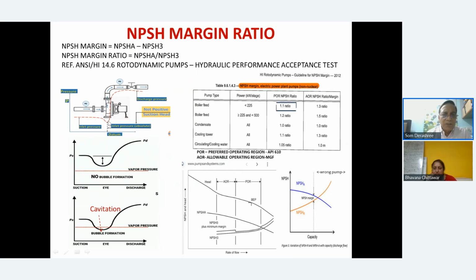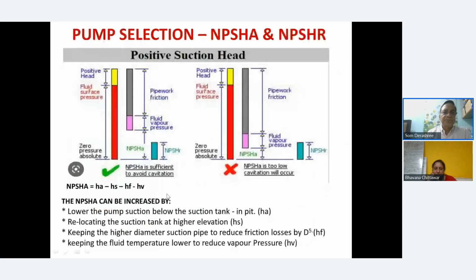Now this fall should stay above the vapor pressure. Let's say this is the vapor pressure line. If it is like this, it's good enough. There will be no problem. But supposing at this point the drop falls below the vapor pressure line, then bubble formation will take place and you will definitely have cavitation. So your NPSH available is this and this is what is required. This is the margin, and it should be followed as per the norms which are given here.